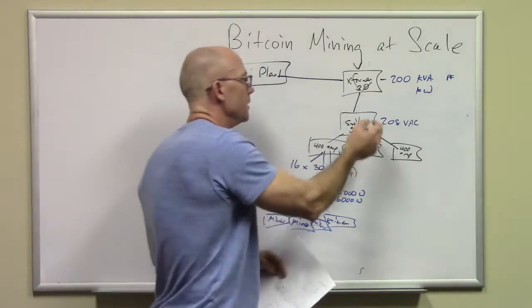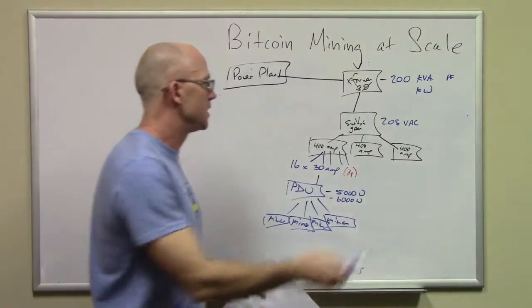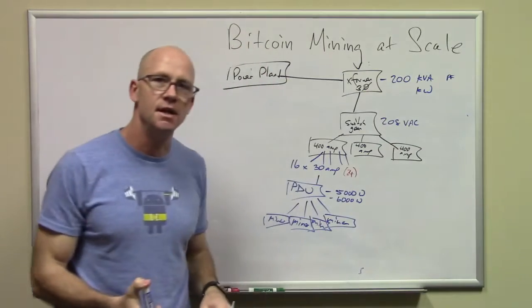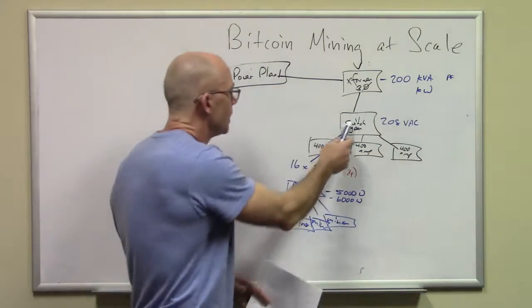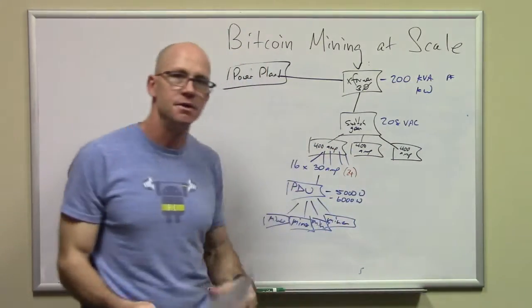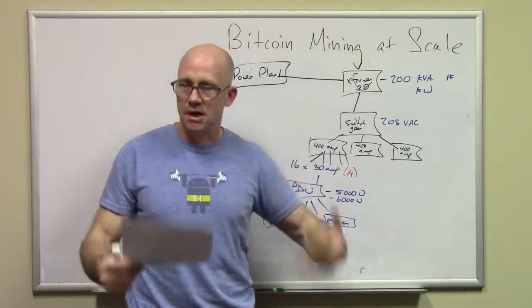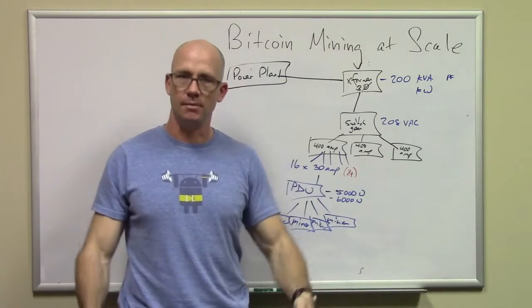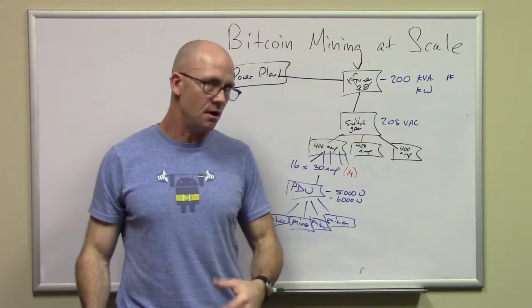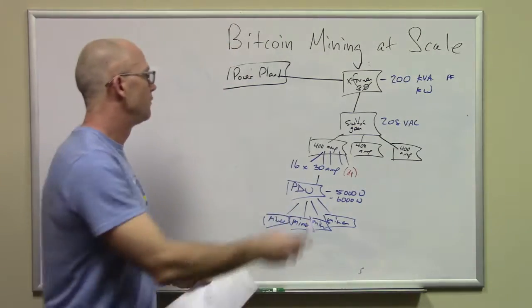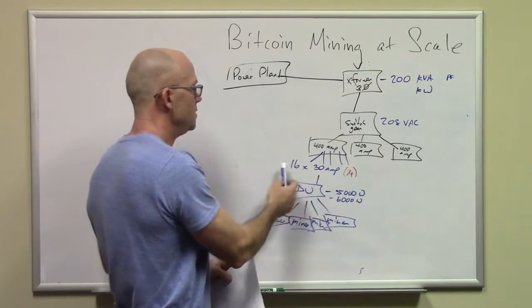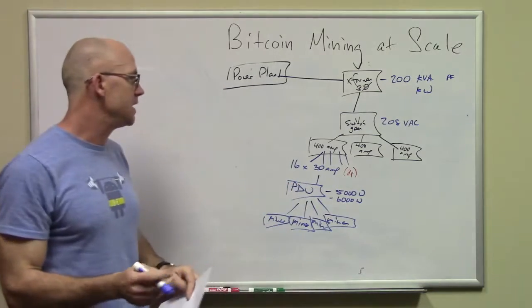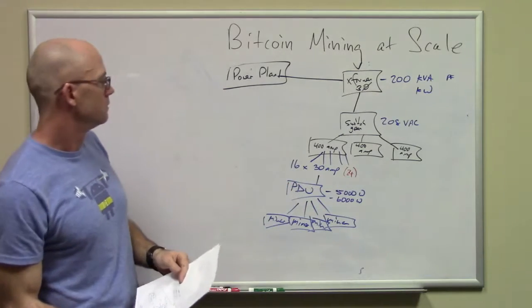Anyway, you bring it into your building and you've got maybe a 1200 amp switch gear. We're talking about 208 volt AC here. One example is you can break it out into 400 amp panels. I like to use common, inexpensive equipment - again, it's all part of keeping the costs low. So from these 400 amp panels, you can break these out into 16 30 amp panels. Is that about right?